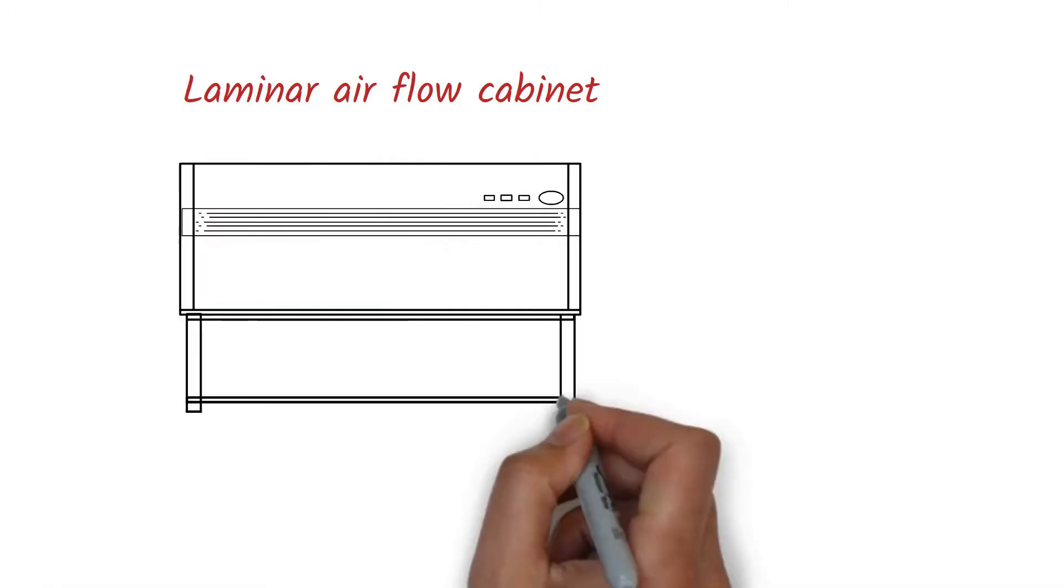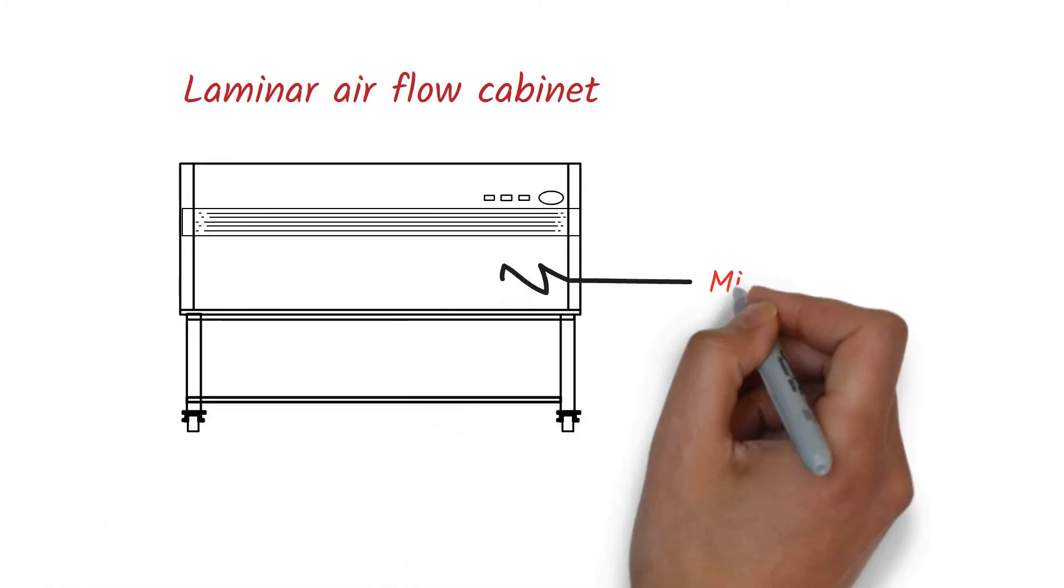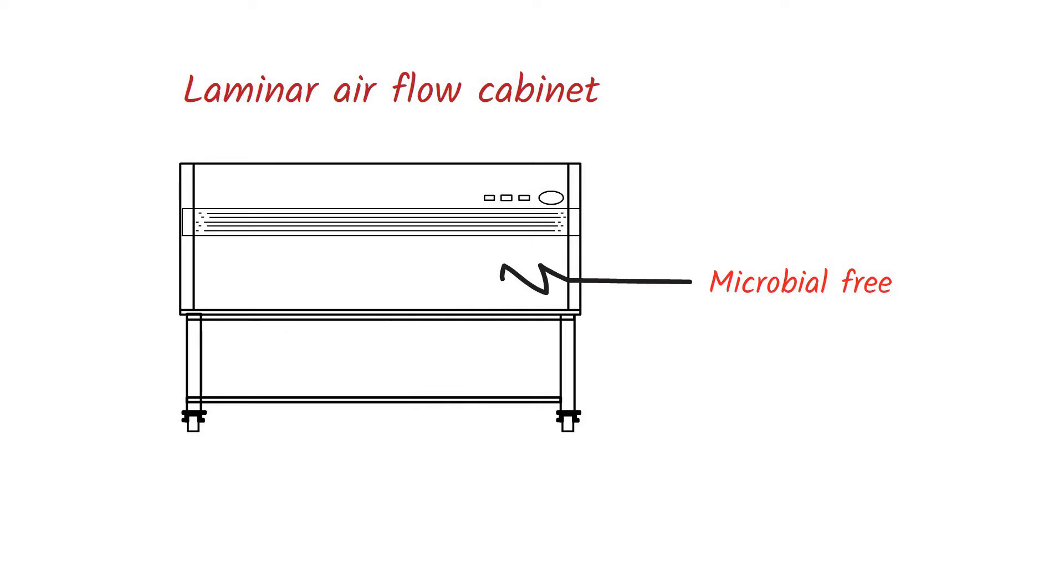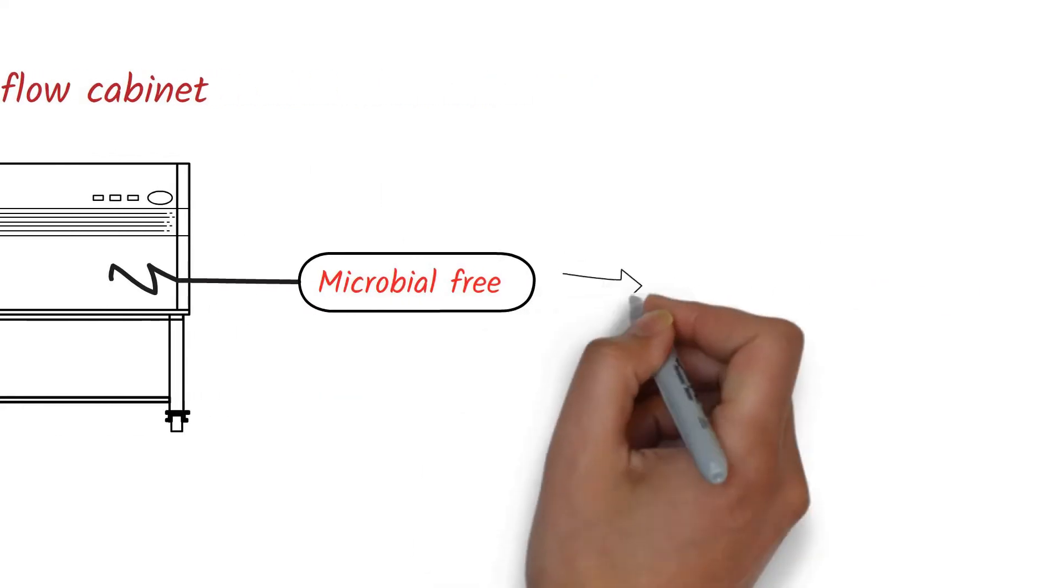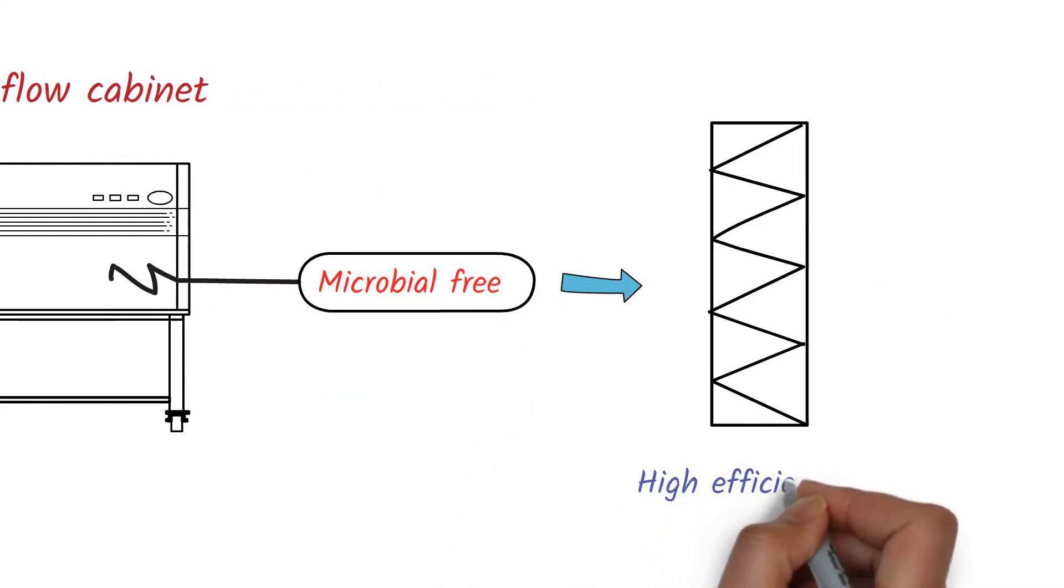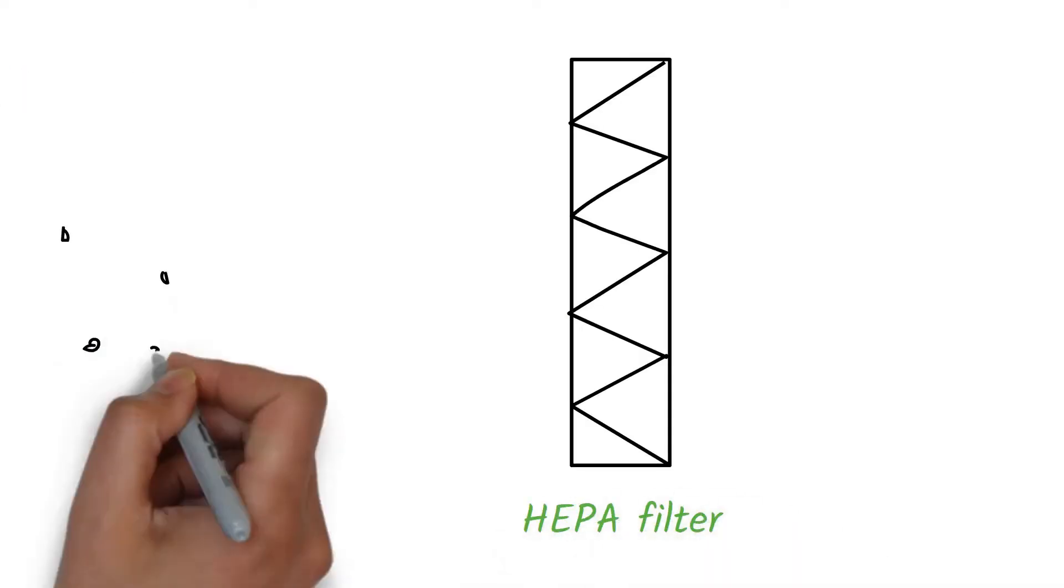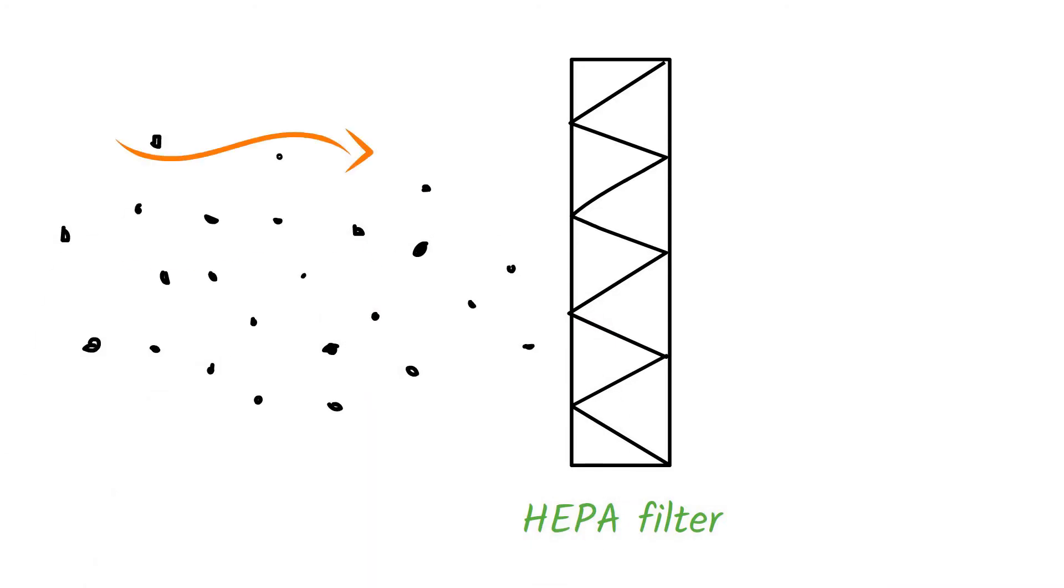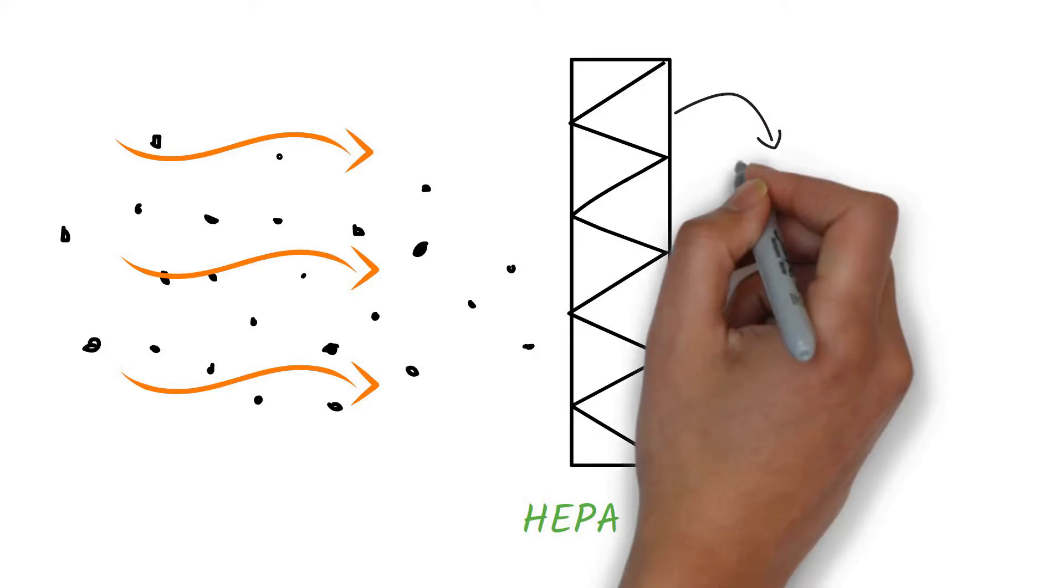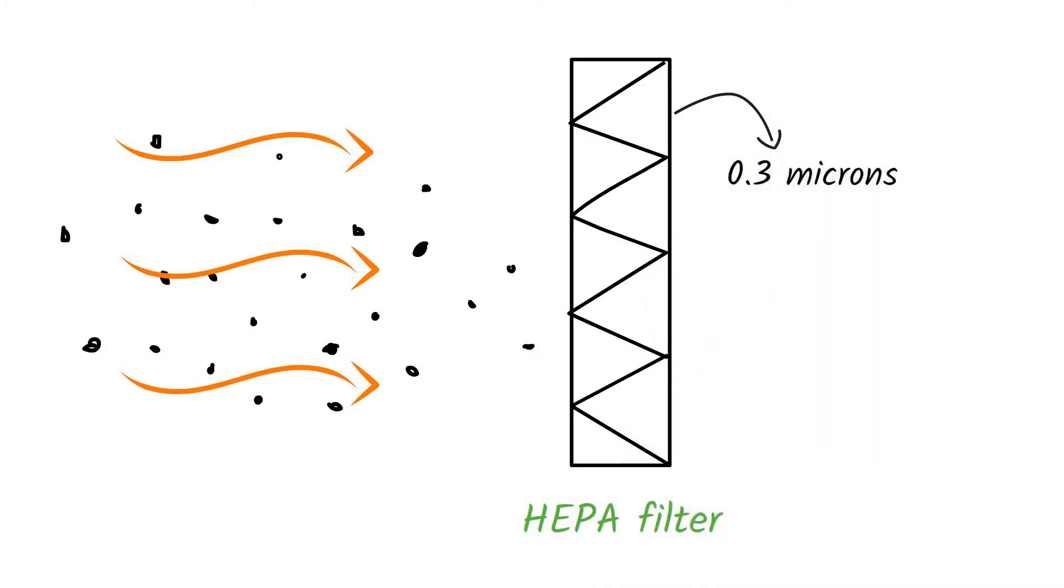A laminar airflow cabinet is an enclosed unit that creates a microbial-free environment. This microbial-free environment is created by high-efficiency particulate air filters, which are popularly known as HEPA filters. These HEPA filters capture all the airborne particles that enter the cabinet. The pore size of HEPA filter is usually 0.3 microns, which can retain bacteria, fungal spores and other particles.